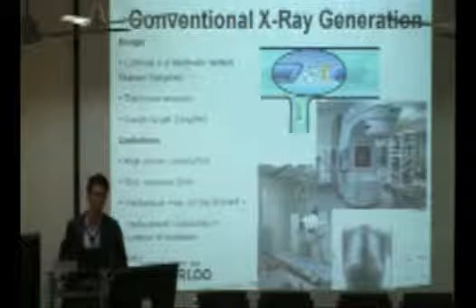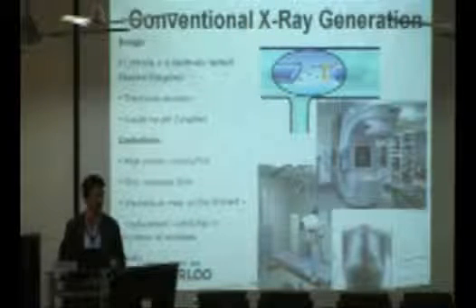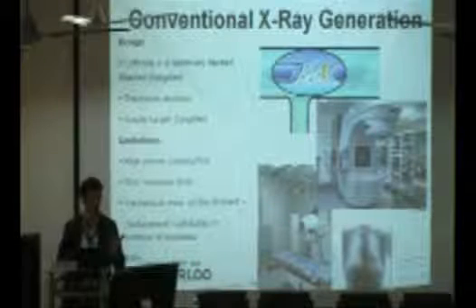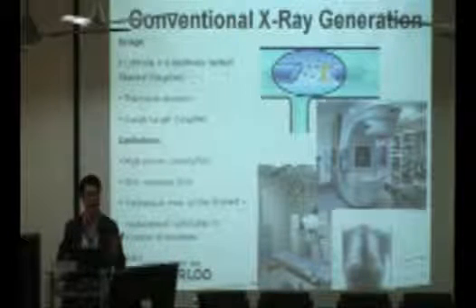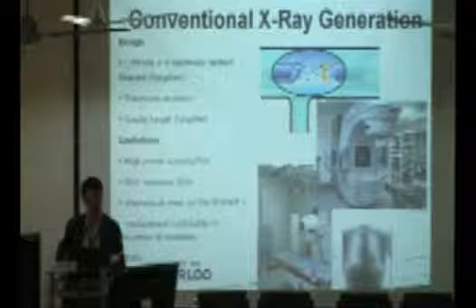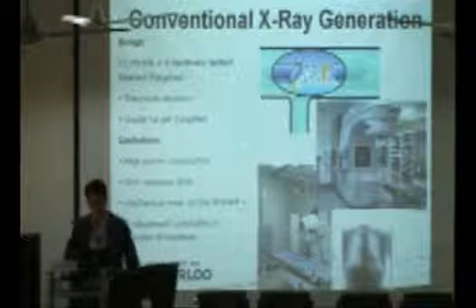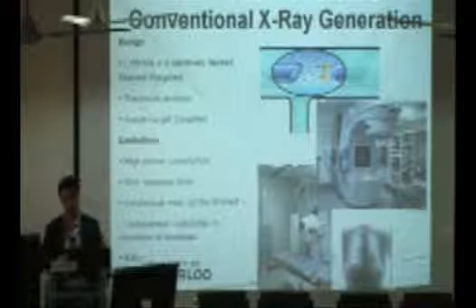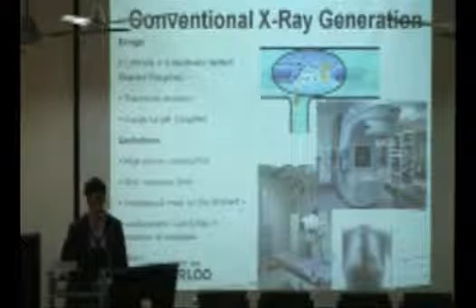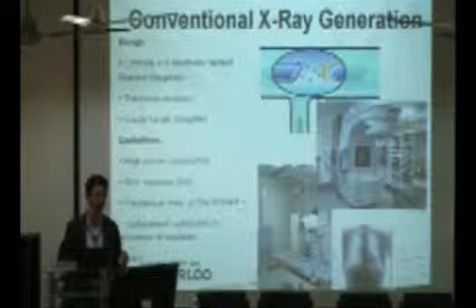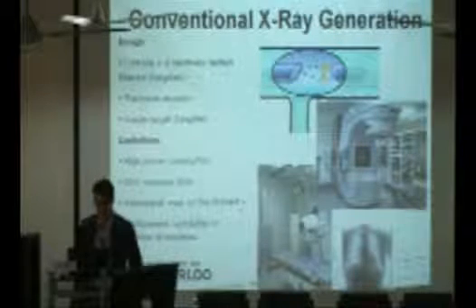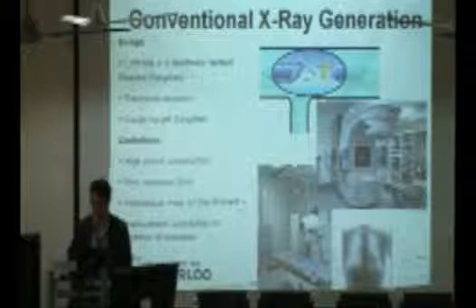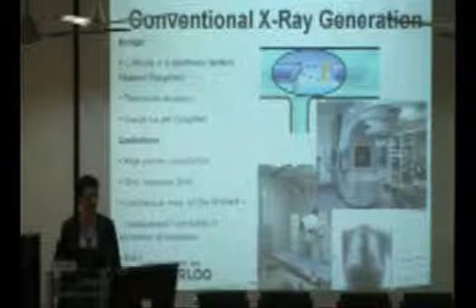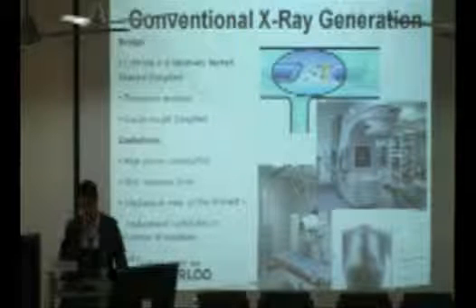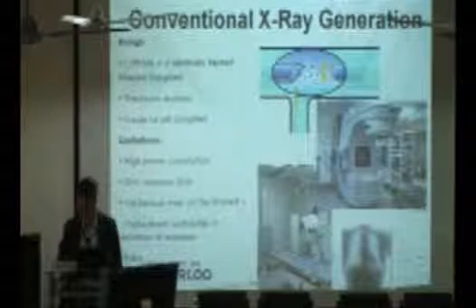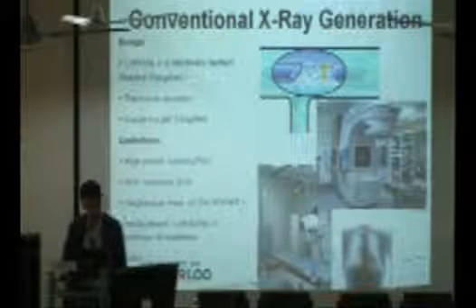Now, besides big and bulky, besides the high power consumption because we have to heat up the metal filament, it also has really slow response because we need to heat up the metal filament. If we want to shut off the X-ray, we need to cool it down. If we want to turn the X-ray back on, we need to heat up the metal filament again. So it really depends on the thermal conductivity of the metal filament, which really governs the time response of the X-ray machine. These are the disadvantages facing us today, but again, we have no clear direction on what to do with this, at least until 5-6 years ago.